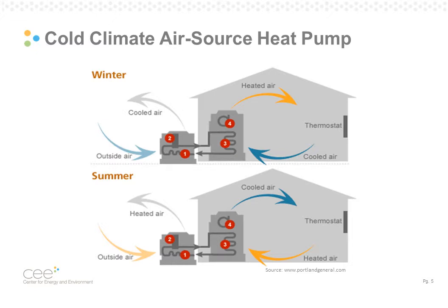What's different about cold climate air source heat pumps is that they have an inverter-driven compressor, which allows the compressor speed to modulate and increase capacity during periods of colder outdoor air temperatures. Manufacturers claim that these new cold climate systems are able to transfer heat into homes at outdoor air temperatures at and below 0 degrees Fahrenheit. With these technological advances, cold climate air source heat pumps have the potential to deliver energy and peak savings, as well as reduce reliance on delivered fuels.